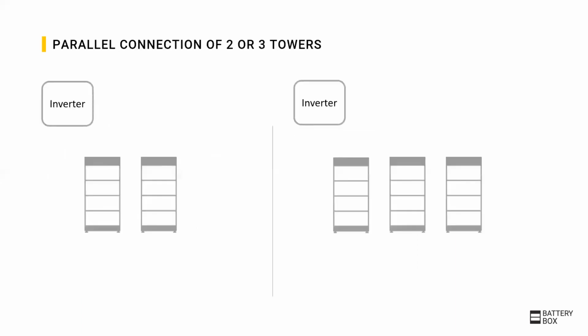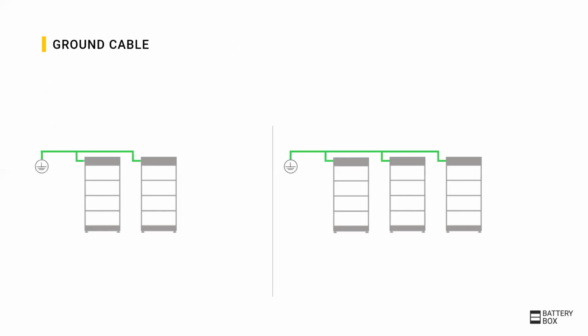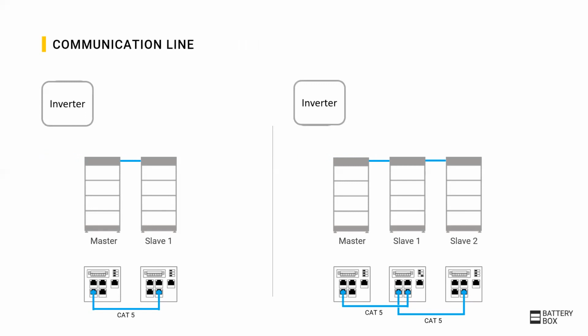Now, the cabling for a parallel connection of 2 or 3 HVS or HVM towers with the same module quantity is described. Each battery needs to be grounded. The batteries will be connected with each other with a normal Ethernet cable. Please make sure to use the correct in and out ports for the parallel connection as shown here. If 3 batteries are in use, the dip switch position of the middle battery needs to be changed according to the picture. The communication cable to the inverter is then from the master BCU to the inverter exactly as you would only connect one battery.